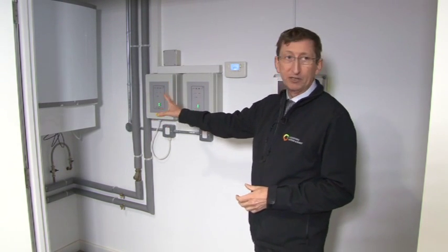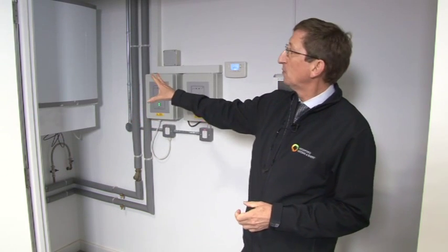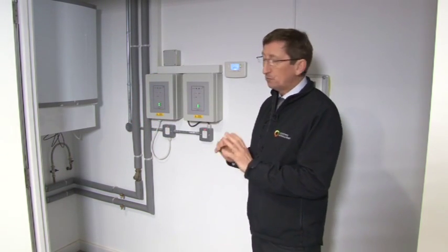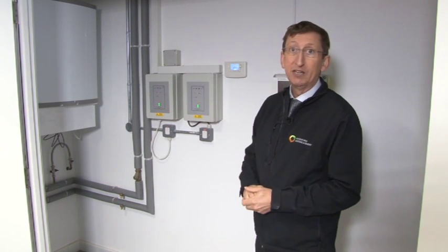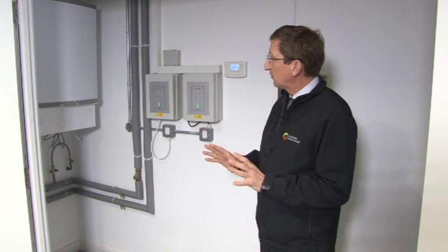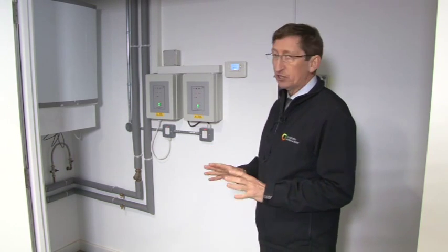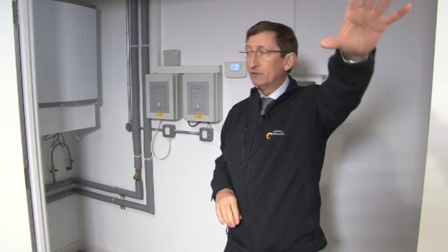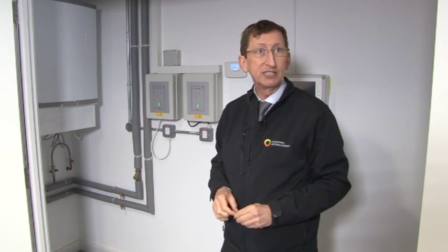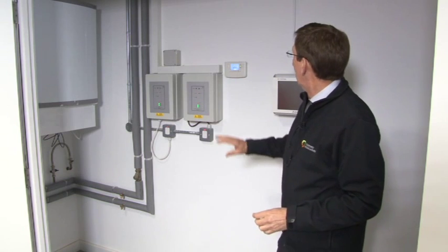So again, it's been fed by the district heating system from the main plant room. Same principle, it's purely heating only in this area. There's no hot water coming off the heat interface unit. But it's feeding a couple of areas, one of which is radiators, which are round in the kitchen area, in the hallway, and the meeting rooms at the back to provide heating into those areas.